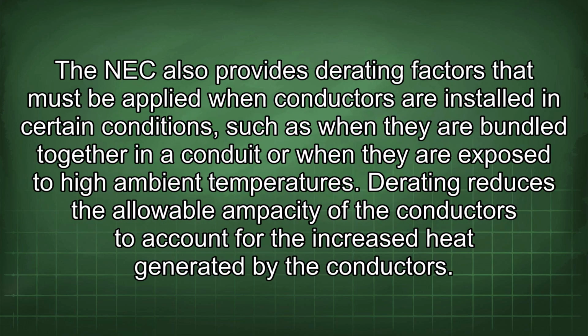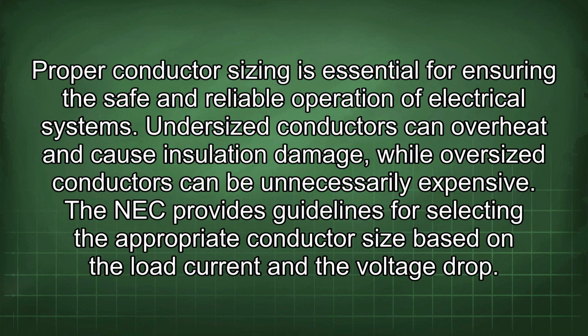The NEC also provides derating factors that must be applied when conductors are installed in certain conditions, such as when they are bundled together in a conduit or when they are exposed to high ambient temperatures. Derating reduces the allowable ampacity of the conductors to account for the increased heat generated by the conductors. Proper conductor sizing is essential for ensuring the safe and reliable operation of electrical systems.